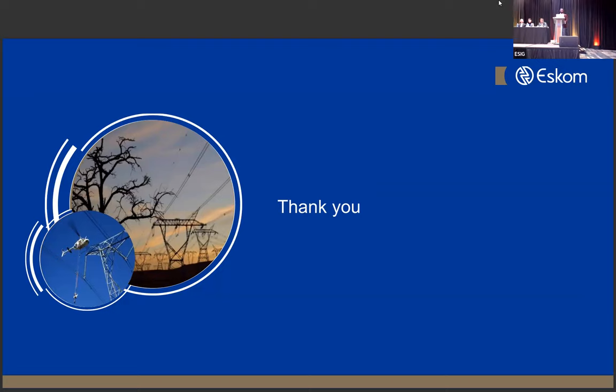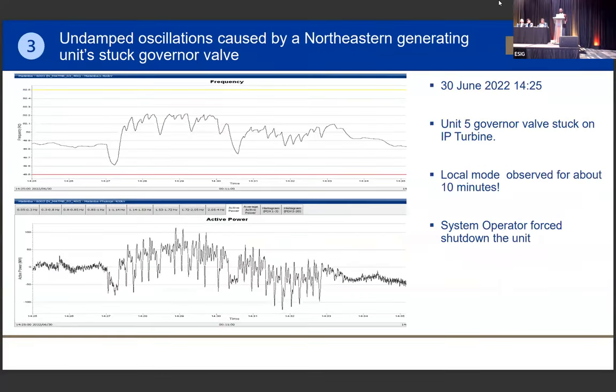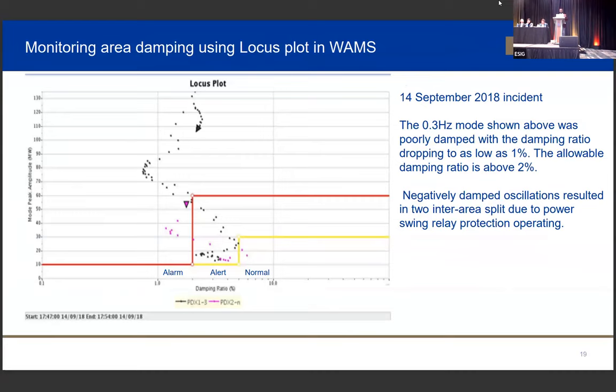Just have a quick question. The oscillations in the control room, if you have a monitoring system, do you have anything monitoring, like alarm and alert showing the gain and the damping of the oscillations? Yes, we do, using the PMU system, WAMS. So live from the locus plot, it shows the damping. Okay, so you have the locus plot, and then it generates the alarm for the control engineers? Yes, so there's an alarm. We can set the alarm, especially for the units that we think are critical. Okay, thank you.